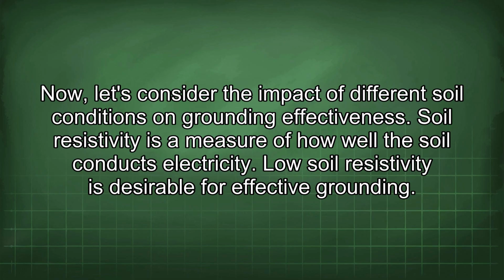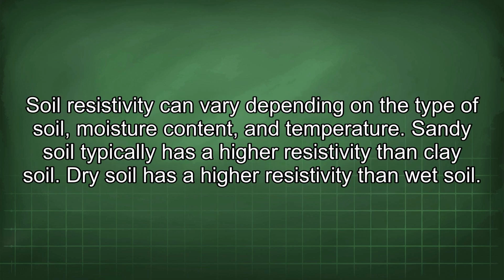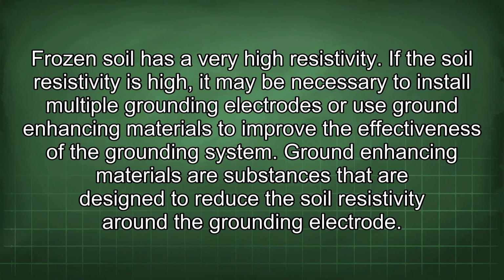Now let's consider the impact of different soil conditions on grounding effectiveness. Soil resistivity is a measure of how well the soil conducts electricity. Low soil resistivity is desirable for effective grounding. Soil resistivity can vary depending on the type of soil, moisture content, and temperature. Sandy soil typically has a higher resistivity than clay soil. Dry soil has a higher resistivity than wet soil. Frozen soil has a very high resistivity.